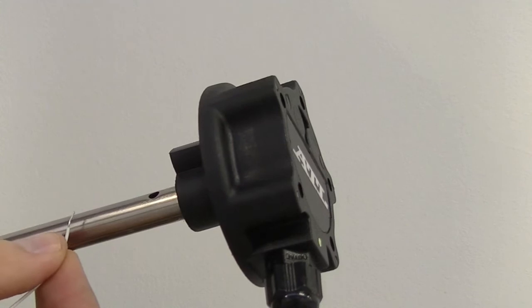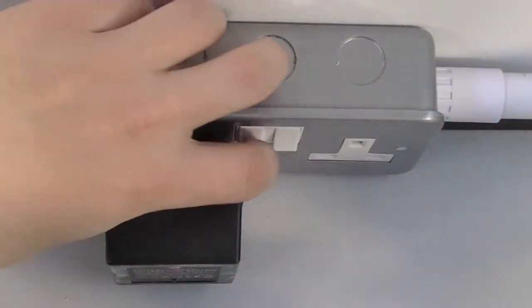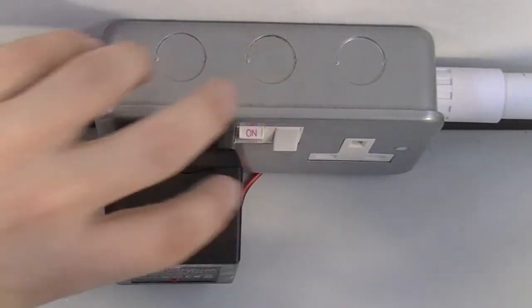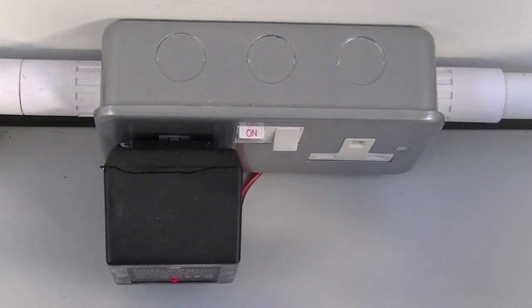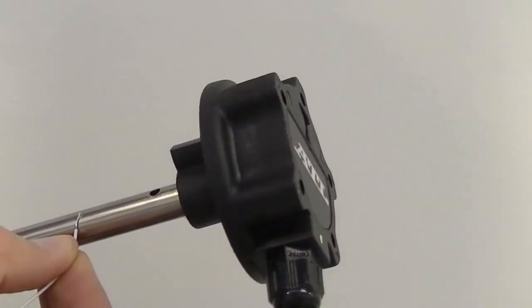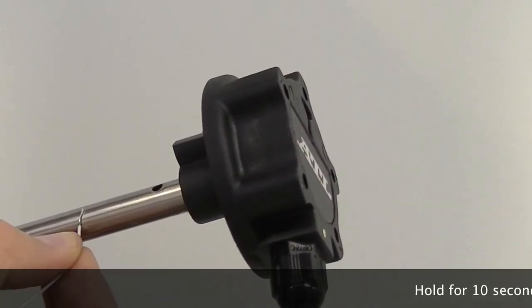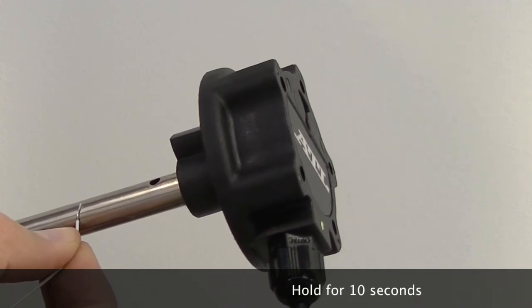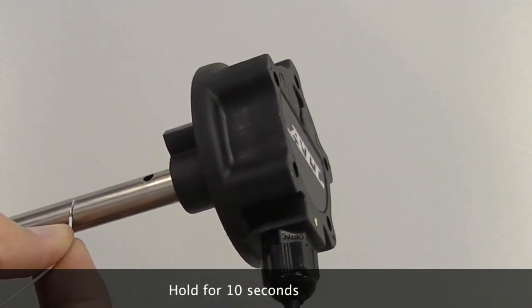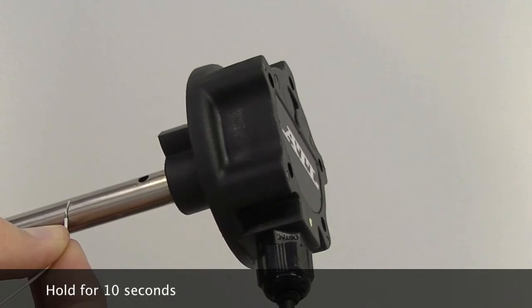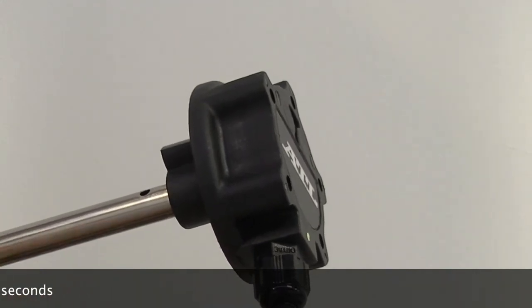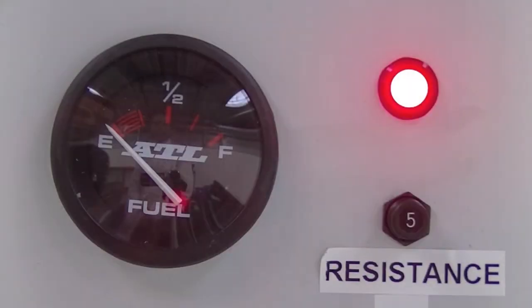Then place the white calibration wire against the sender tube and power back on the system. Hold the calibration wire against the sender tube for 10 seconds. This has calibrated the empty point of the sender.